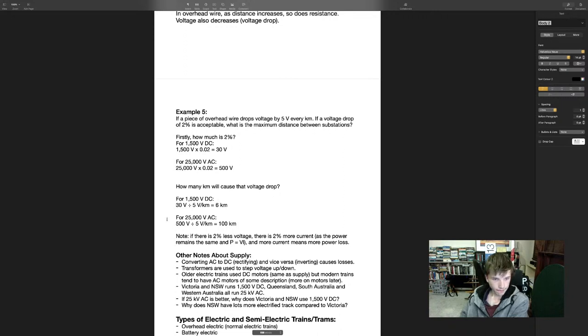Sounds all right. For 25 kilovolts, now we divide 500 by 5, which is 100. Okay, so yeah, you can really see there that that's one of the reasons why 25 kilovolts has a lot higher distance between substations, because we can drop the voltage a lot more before we need to renew it.